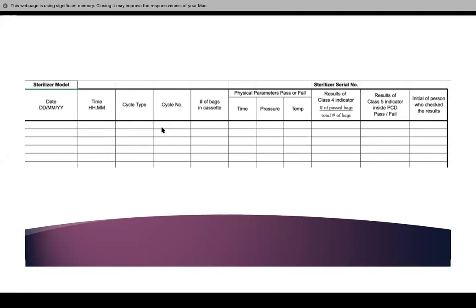And then the cycle number. There is a load number — that is what goes on your bag as well. Then the number of bags or cassettes in the autoclave. Then the physical parameters: time, pressure, and temperature. The results of the class 4 indicator and the results of the class 5 indicator inside a PCD — is it a pass or a fail? Also, the initials of the person who has checked the result.